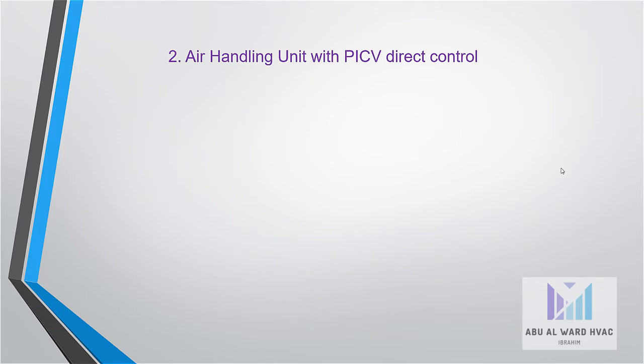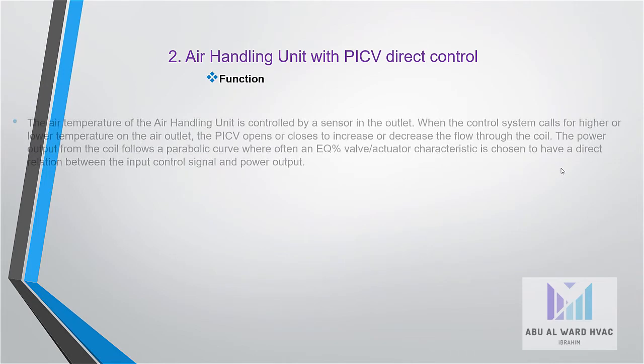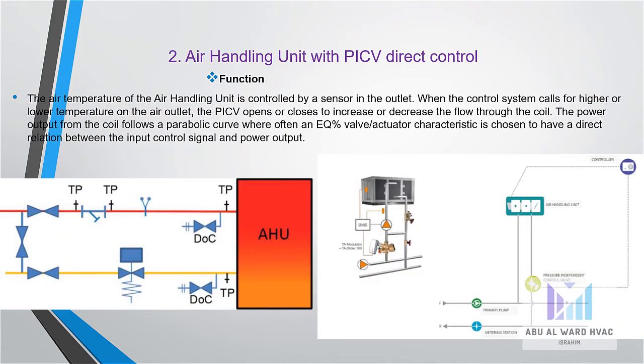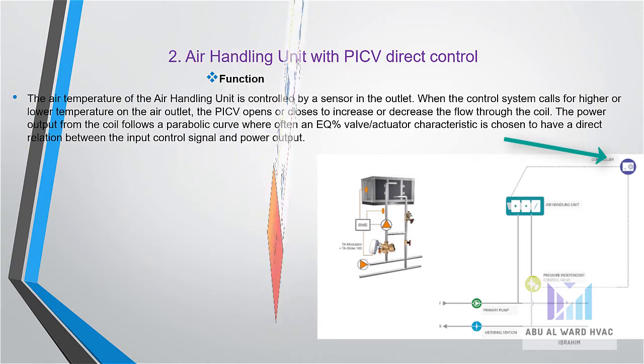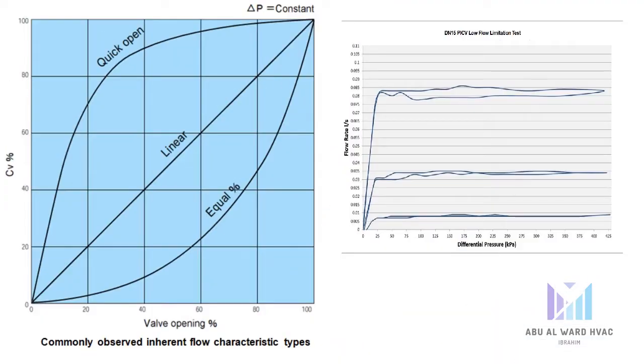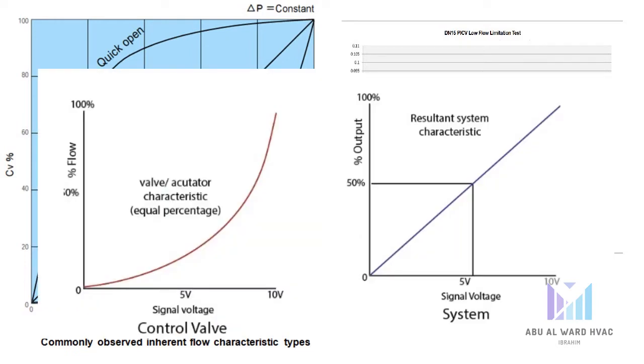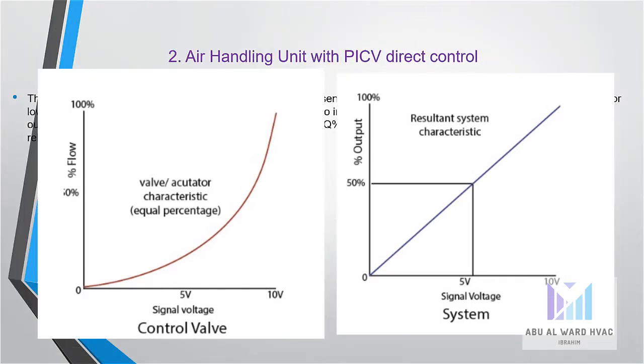Air handling units with PICV direct control. The function: the air temperature of the air handling unit is controlled by a sensor in the outlet. When the control system calls for higher or lower temperature on the air outlet, the PICV opens or closes to increase or decrease the flow through the coil. The power output from the coil follows a parabolic curve where often an EQ percent valve/actuator characteristic is chosen to have a direct relation between the input control signal and power output.